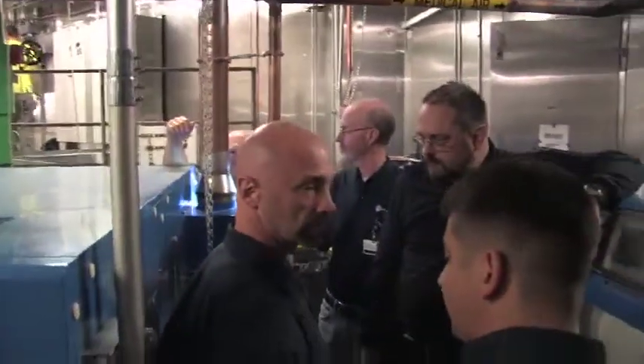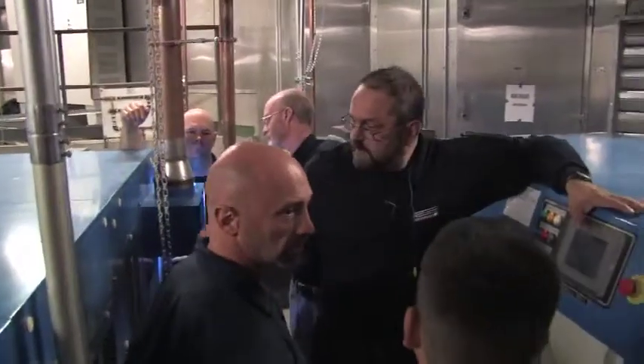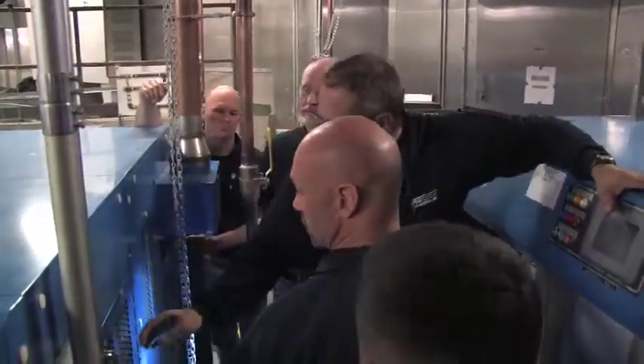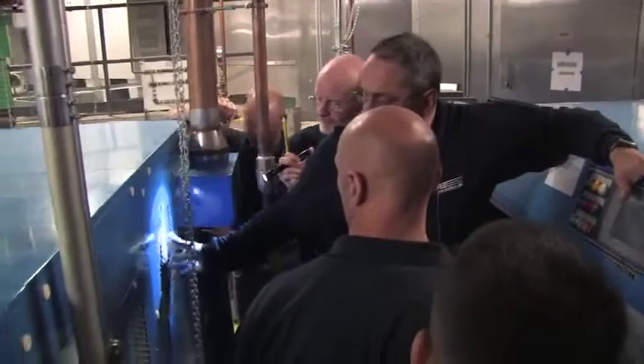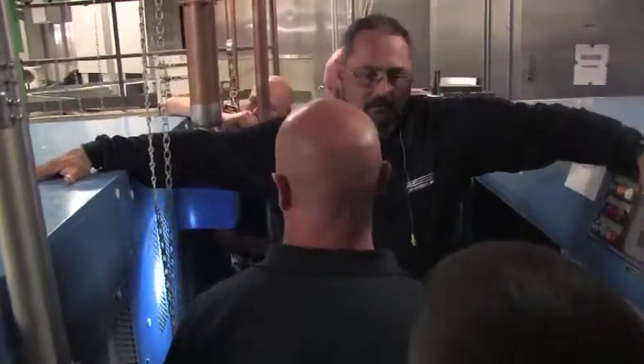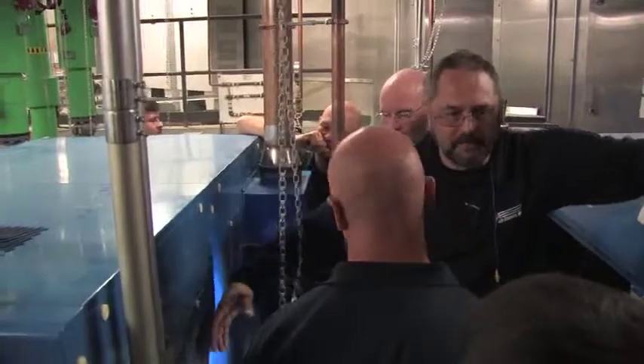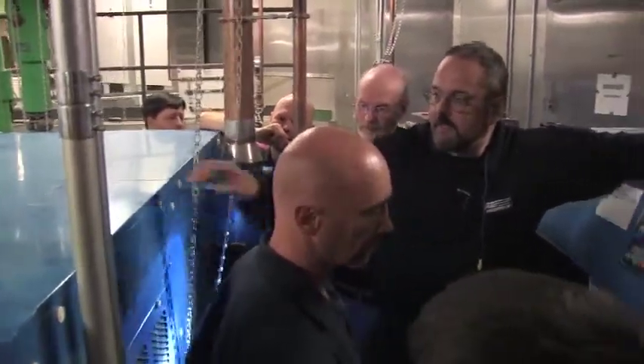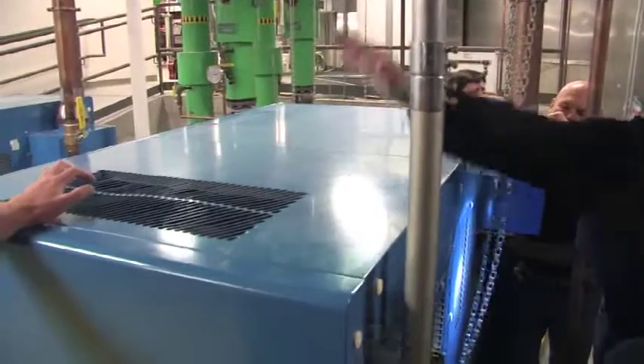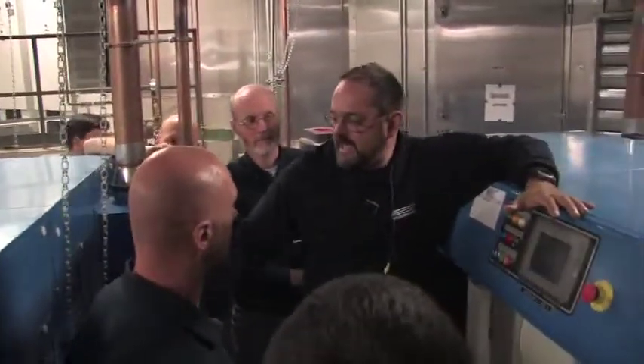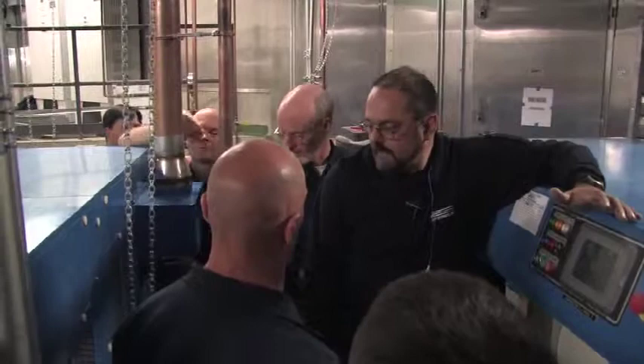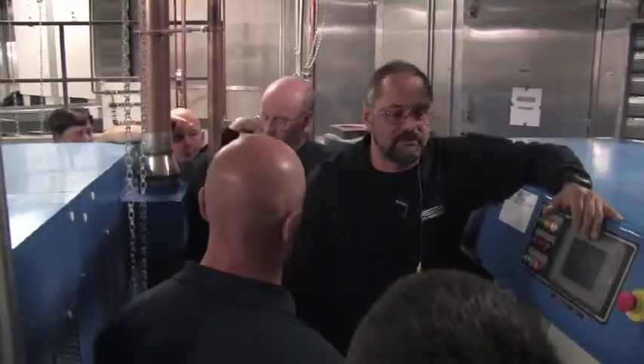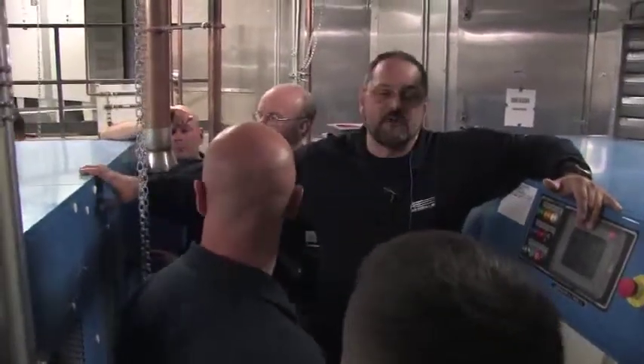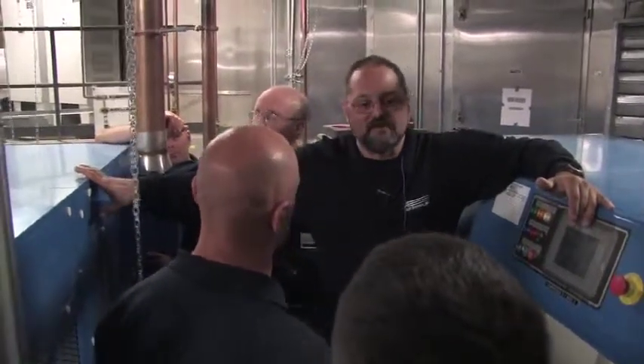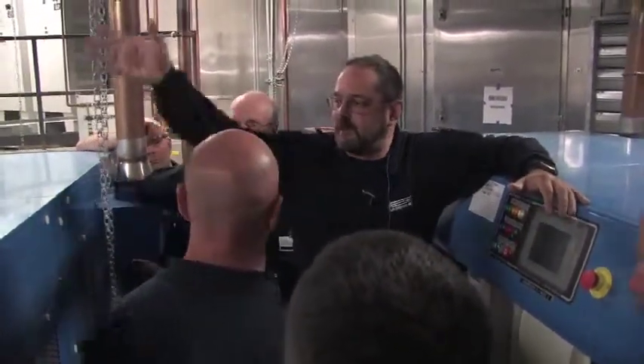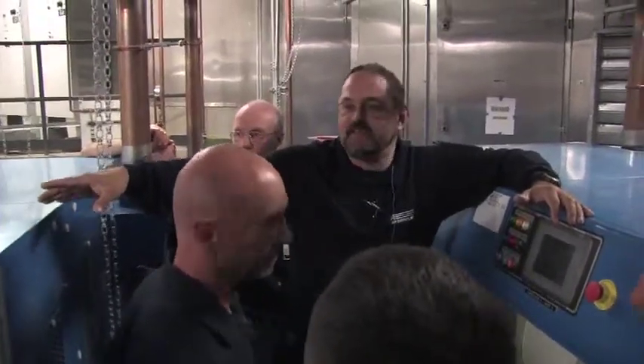How crucial is it to keep these clean? That's monthly. Yep. This one here is the cooling air getting pulled in across the cooler. This one is the cooling air getting pulled in across the motor and the air ends. And everything goes out, blown out by the fan out the top. So if that gets clogged, and I don't think it'll be a problem here. The fun thing we get sometimes is, that's a nice flat surface. It's amazing how fast it overheats when somebody puts a 40-pound box on top of the cooling vent.